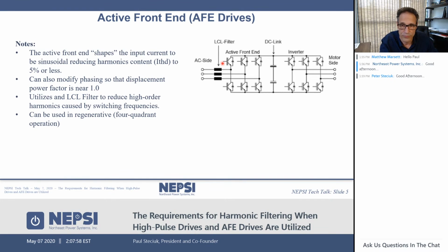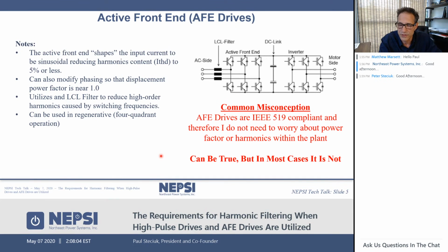I just ran into a project that had that going on. It was a crane operation project. So it's interesting to note that a resonant condition can occur and it needs to be modeled. It forced our system to go from a normal notch filter to a high pass type filter system.